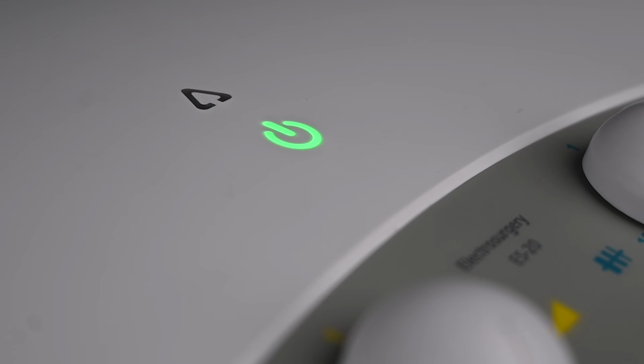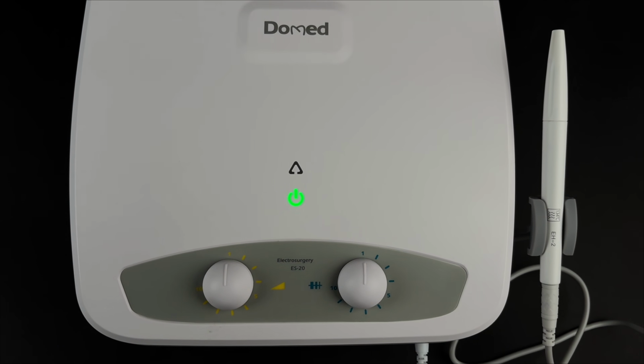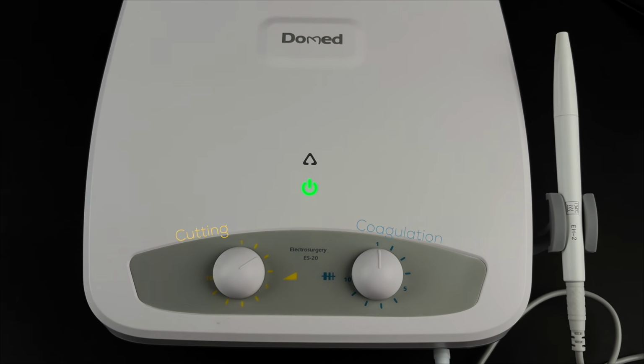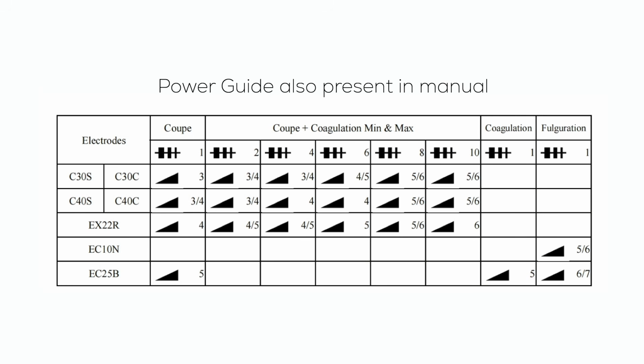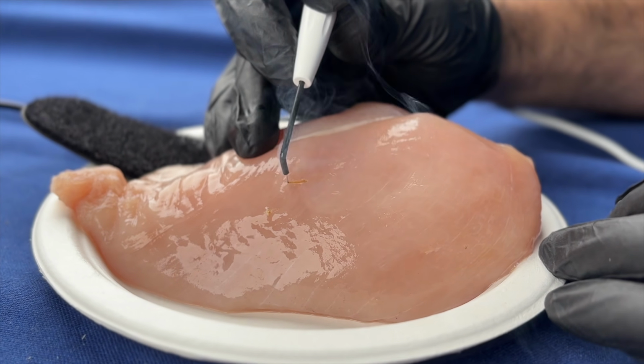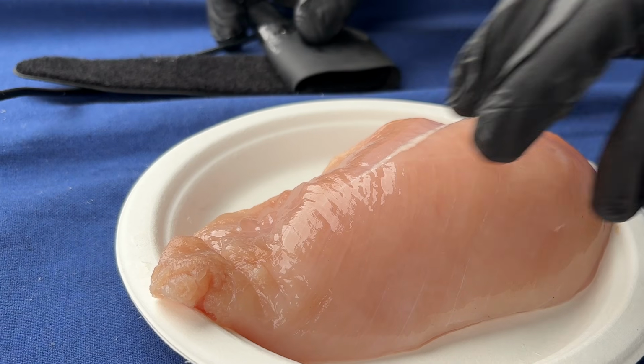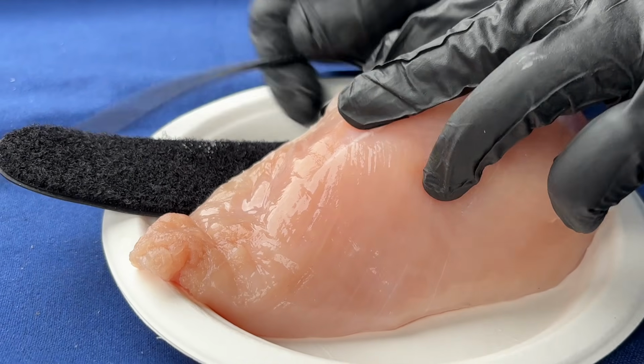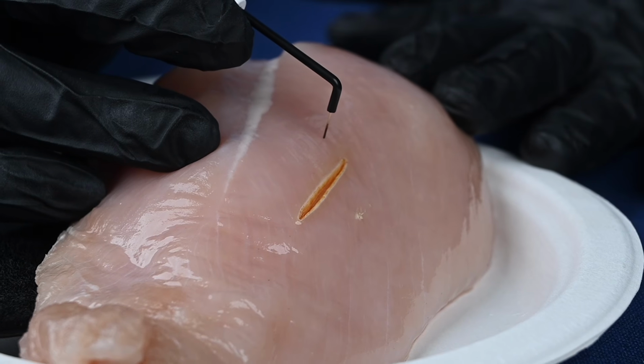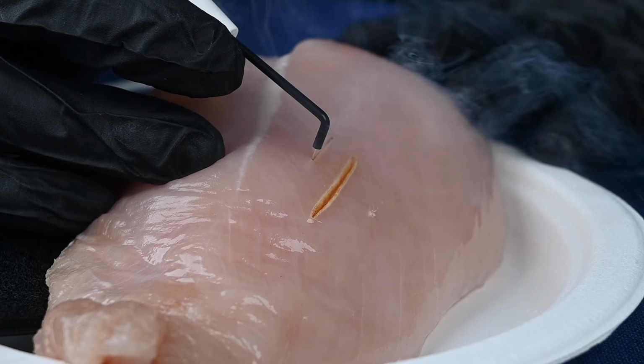As we power on our unit, we have two knobs, one for the cutting and the coagulation, which has variable values between 1 and 10. For this example, we are using a chicken piece with a grounding electrode underneath it. This is the incision action using a needle electrode.